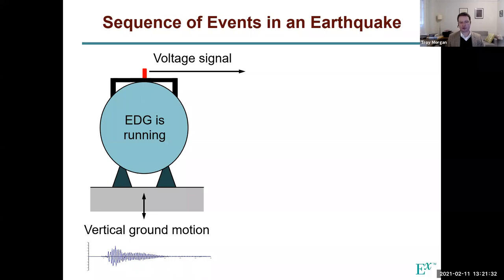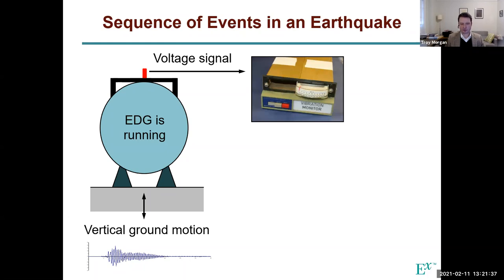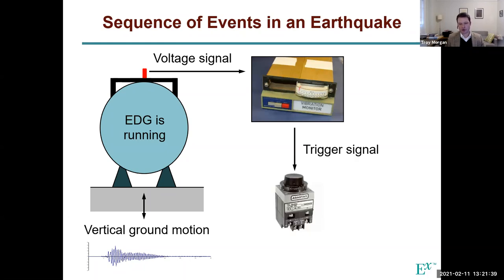And then you get a voltage signal that comes out as a result of the shaking. That voltage signal goes to a vibration monitor. That vibration monitor then sends a signal to a trigger. This is called an Agastat relay, and it basically measures the amount of charge that gets stored up over time. And if it exceeds a certain amount for a certain duration, it says, all right, this thing's malfunctioning, trip it off. And if it doesn't meet that criteria, it says, no, it's fine. You don't need to trip it off. Just let the thing keep running.